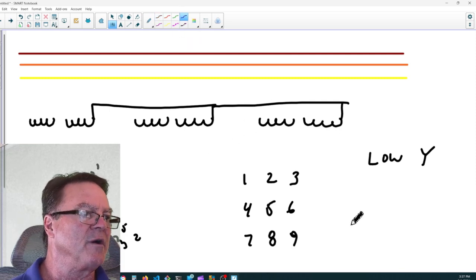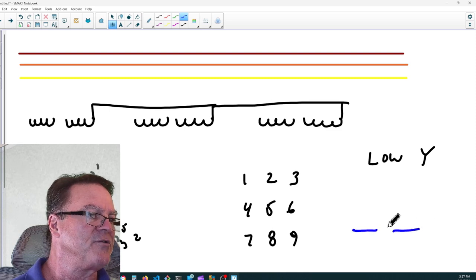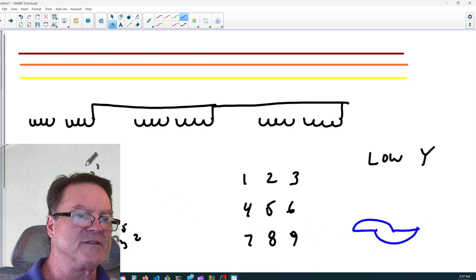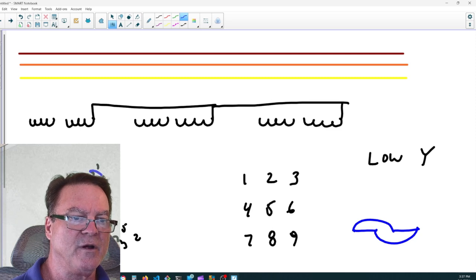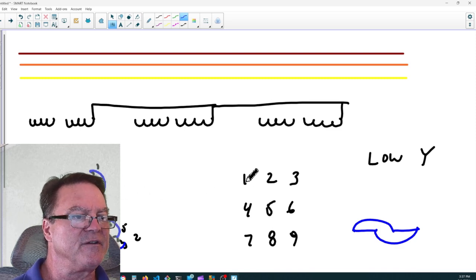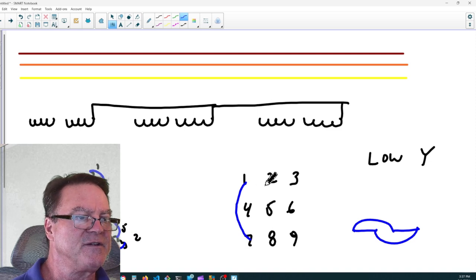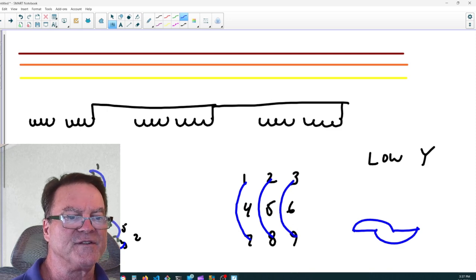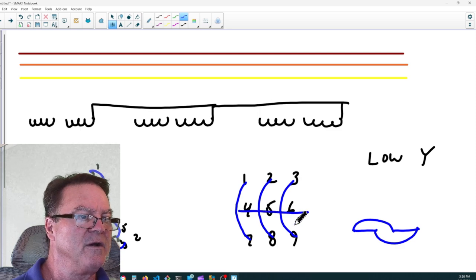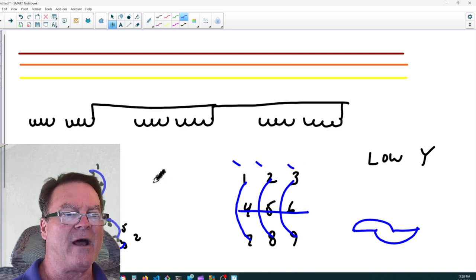And in order to do that, we're going to draw an airplane propeller. And here's how you draw an airplane propeller. You leapfrog over the second, then go to the third, and you do that. That's an airplane propeller. So I'm going to take this and go whoop, whoop, whoop, whoop. And so what we have is 1 goes to 7, 2 goes to 8, and 3 goes to 9. 4, 5, and 6 meet together in the middle for the star. There's 4, 5, and 6, and they're hooked together. And 1, 2, and 3 are our lines out.